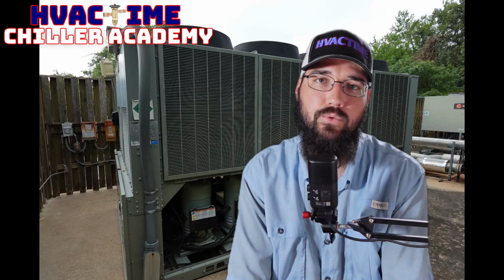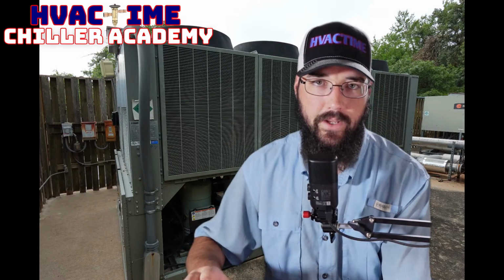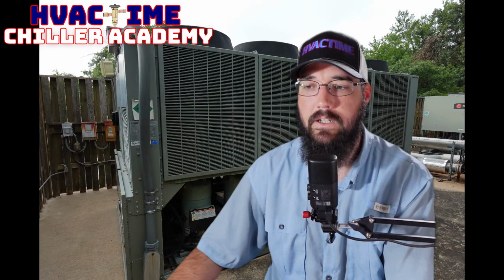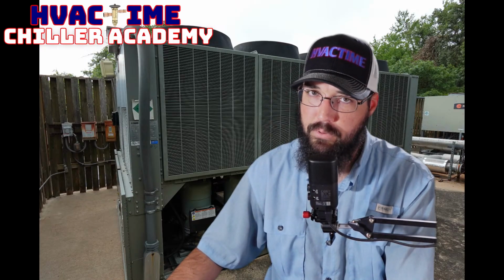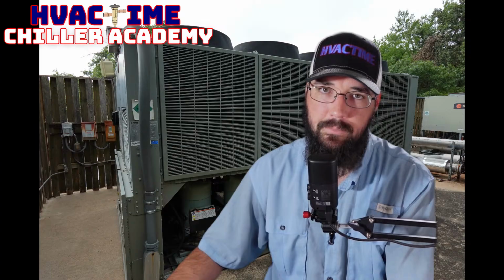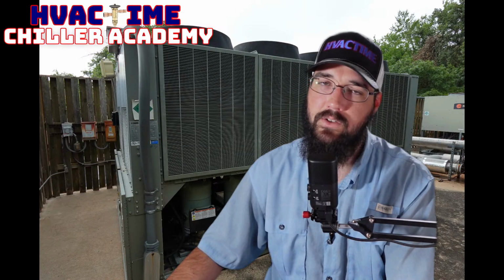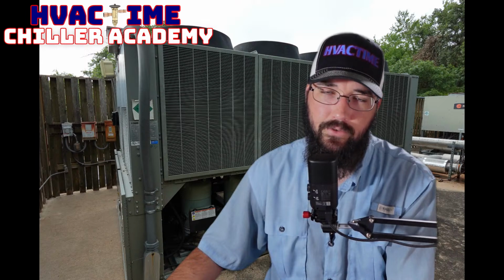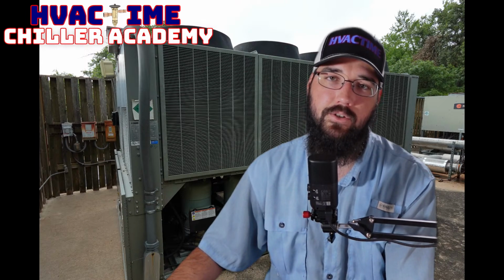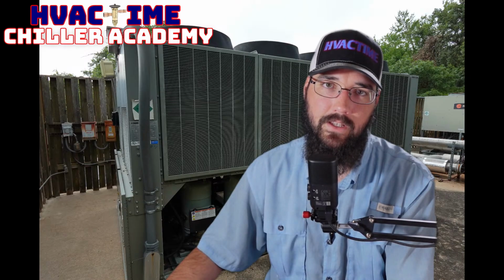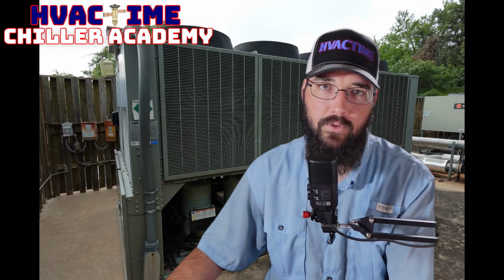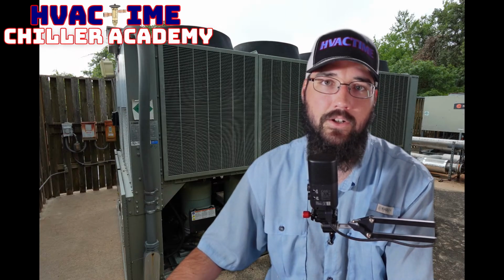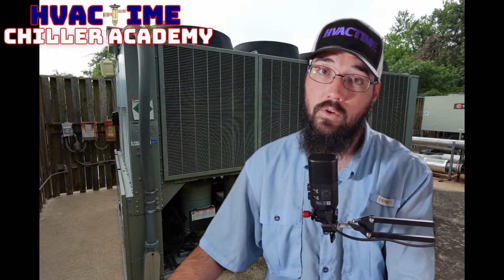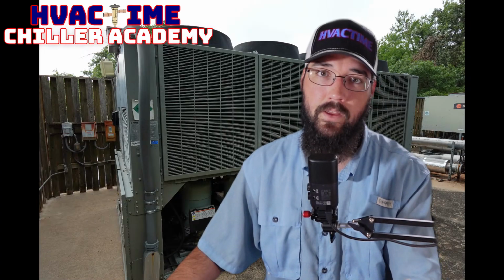Like, they have to, again, the corrective factor has to be there to adjust for that. There's other ways of doing that that doesn't short cycle the chiller. But I would put money down that they're trying to energy optimize, and that energy optimization tells them that this is a good idea, and I disagree. And this is why I have such problems with energy optimizers, because they get these ideas and they don't understand the inductive load concepts and motors and the whole bit. Like, they're not trained at that level. They don't know. They think they know more than they do, and that's okay. Most of us do.